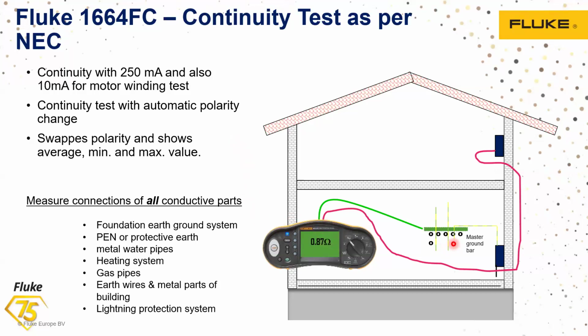So what happens here? When you connect the device to the different systems in your electrical installation and you want to measure the continuity, once you press the test button, the multifunction tester has to inject a minimum of 250 milliampere current. This test is done on all conductive parts. It may be a foundation, the earth ground system, or protective earthing, metal water pipes or heating systems, or other wiring or lightning protections connected in your facility.